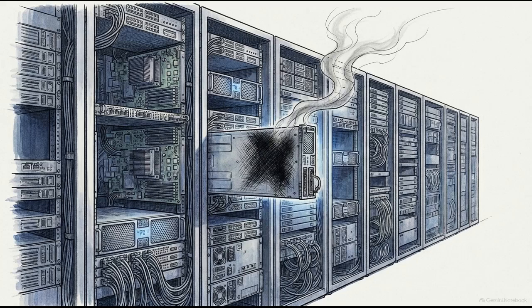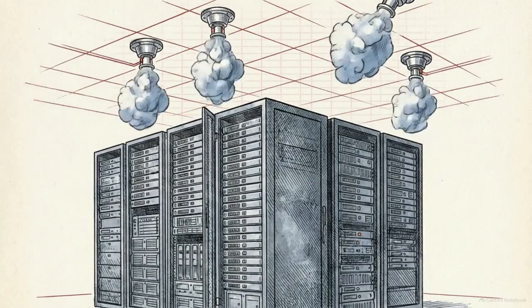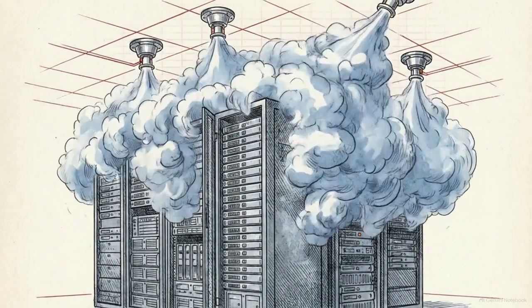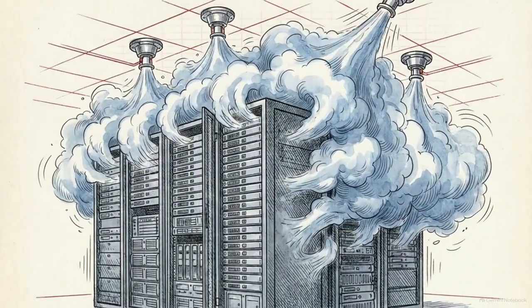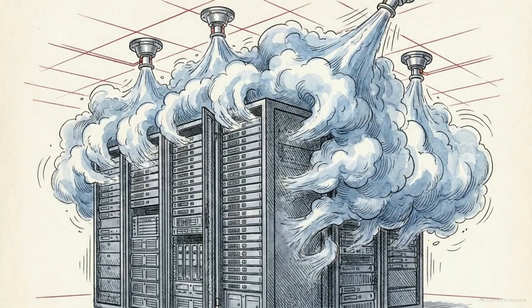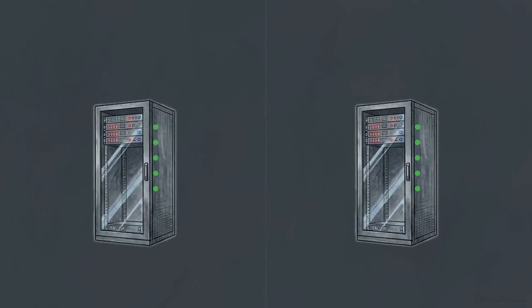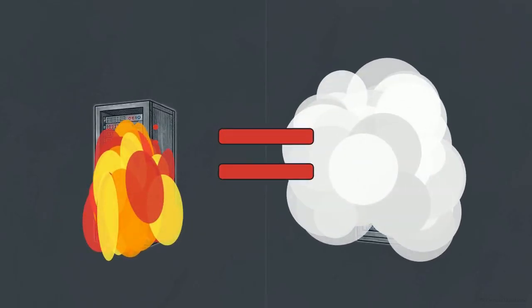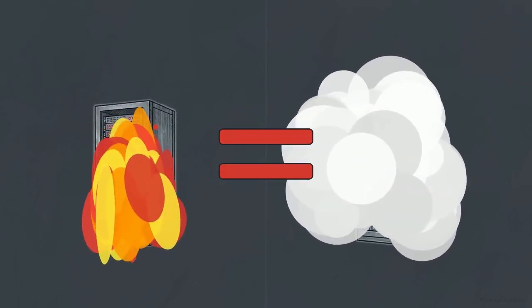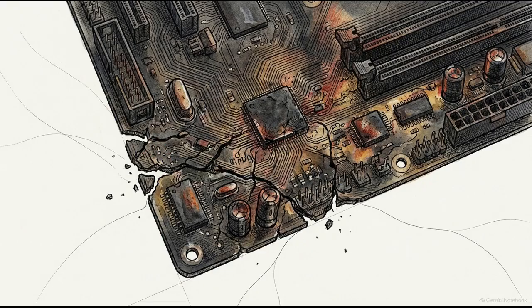Imagine a catastrophic IT outage triggered not by a server failure or a massive electrical fire, but by the system designed to protect the building. A single faulty sensor reading releases a cloud of suppression gas that floods the data hall. In mission-critical environments, a false suppression discharge is financially equivalent to an undetected fire. Both result in millions of dollars in downtime, hardware damage, and total operational failure.